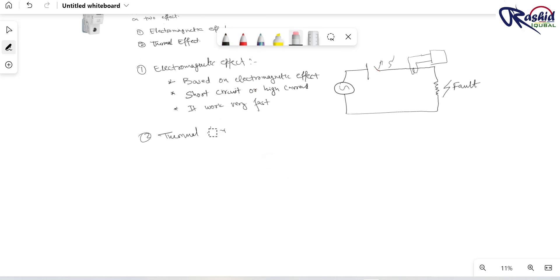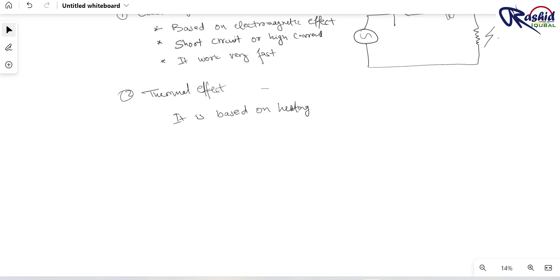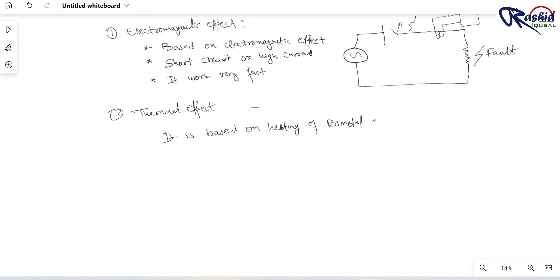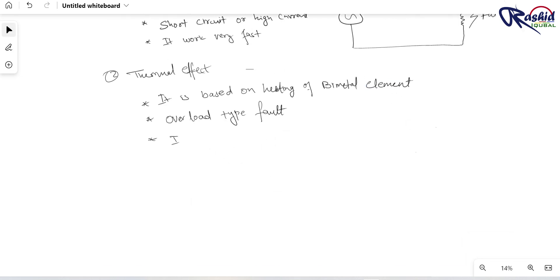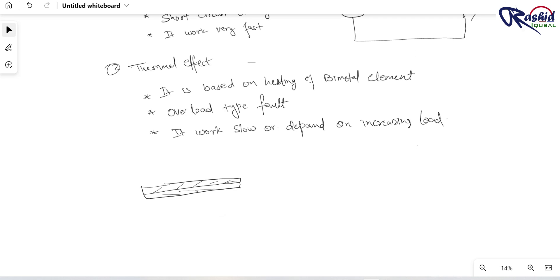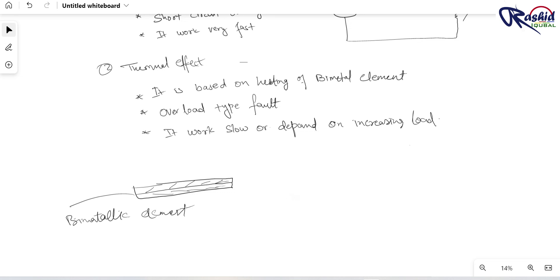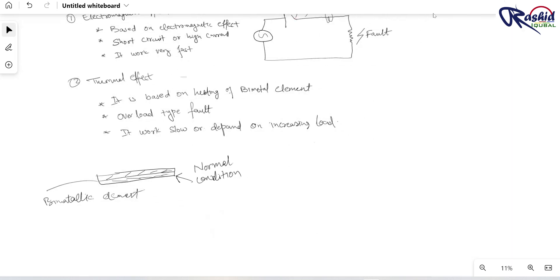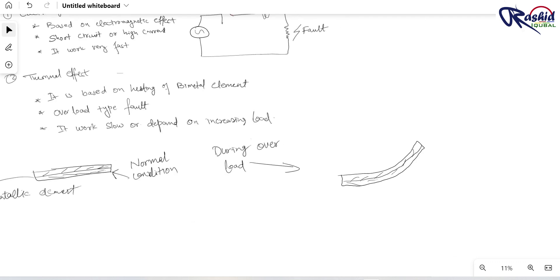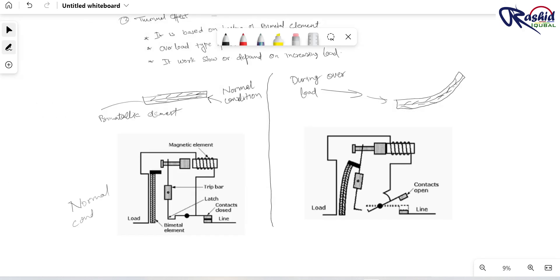Now second, we will discuss the thermal trip. It is based on heating of a bi-metal element. This is an overload type fault, and it works slowly, depending on the increasing load. There is a bi-metal strip which is made up of two types of metal. When heating takes place due to over-current flow, one metal of the strip expands more and another expands less, so this bi-metal strip gets bent due to heat. Because of this movement of the bi-metal, there is an arrangement in the breaker whereby the contact becomes open and the MCB gets tripped.